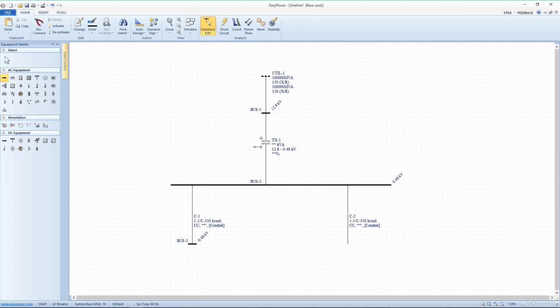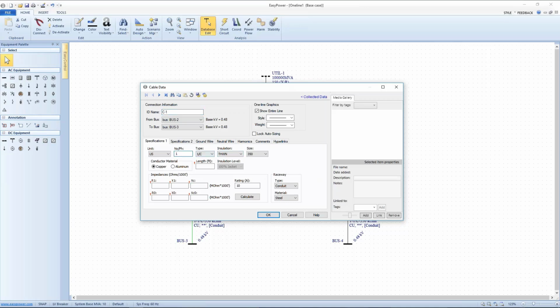And so what he described now was the contents or the data that he had collected for his one-line diagram. He said, double click on this first cable. It's a single conductor per phase. It's a single core cable, so it's 1C. It's an outside wiring system, so it's THWN insulation. He said it's a 350 kcmil cross section, and this first cable is 50 feet long. Now the tool, once I've described this copper conductor flowing through its steel conduit, will actually calculate for me the cross-sectional ampacity and the positive sequence and zero sequence impedance, both the resistive and reactive impedance of the cable. Quite literally the most accurate impedance calculations in the industry.